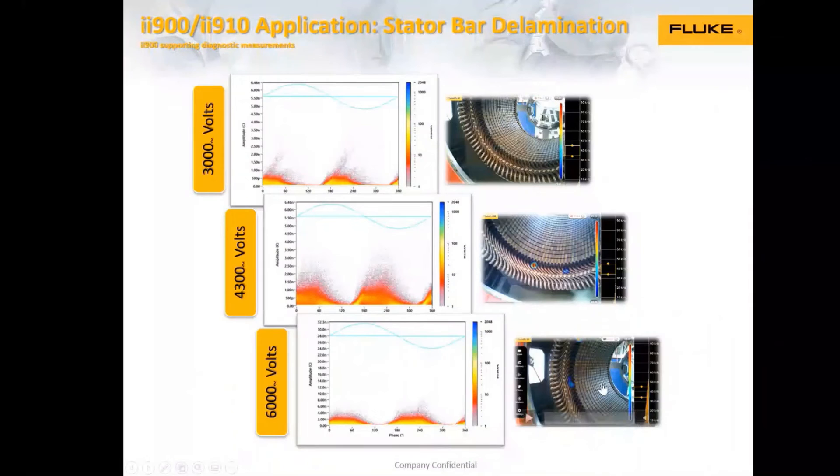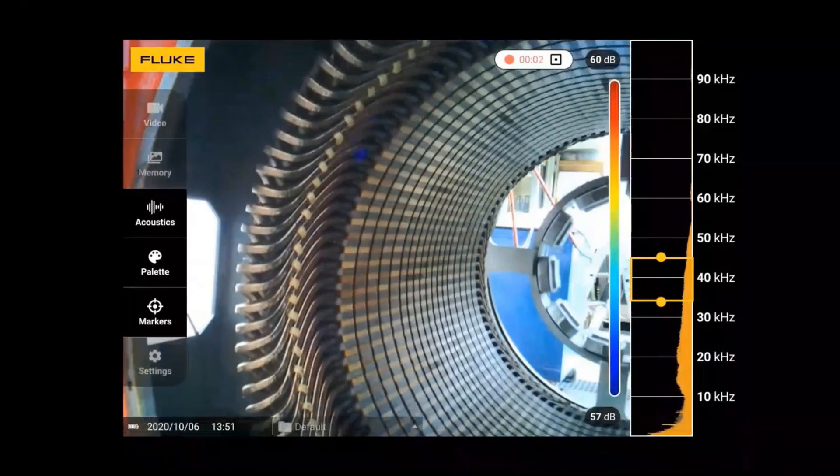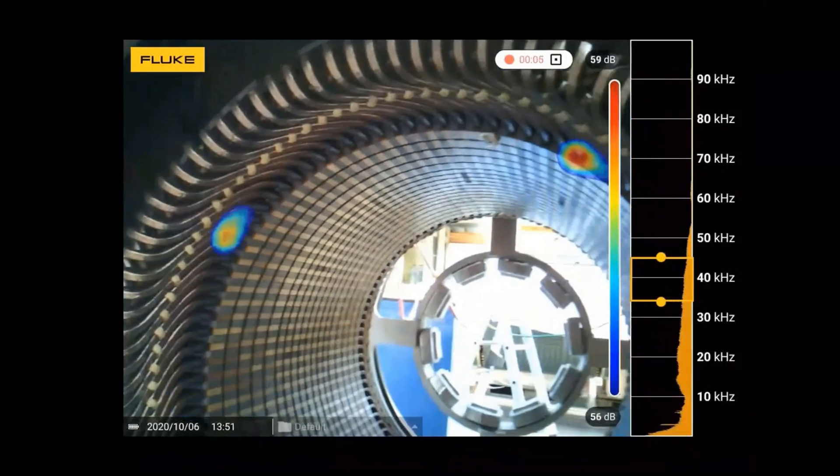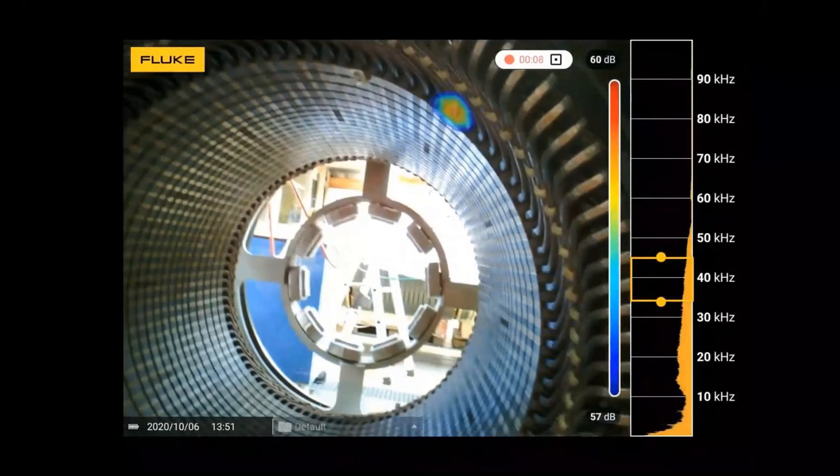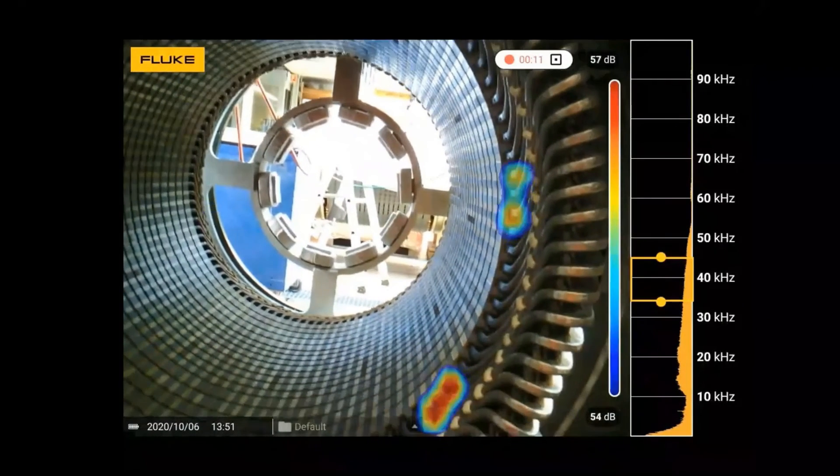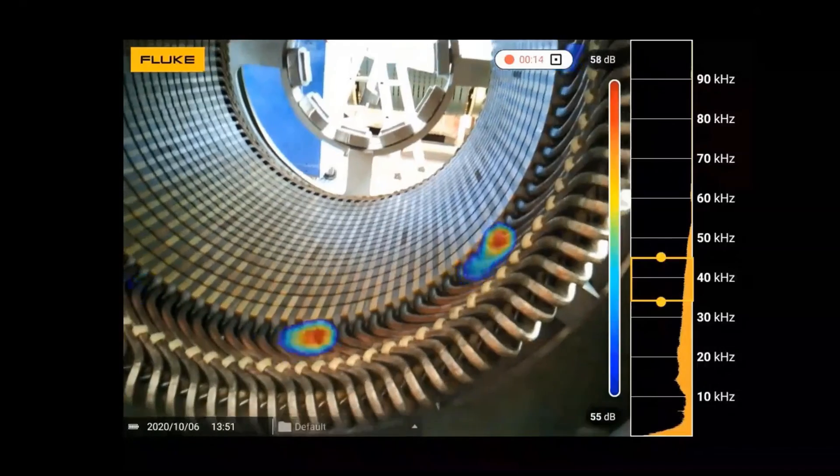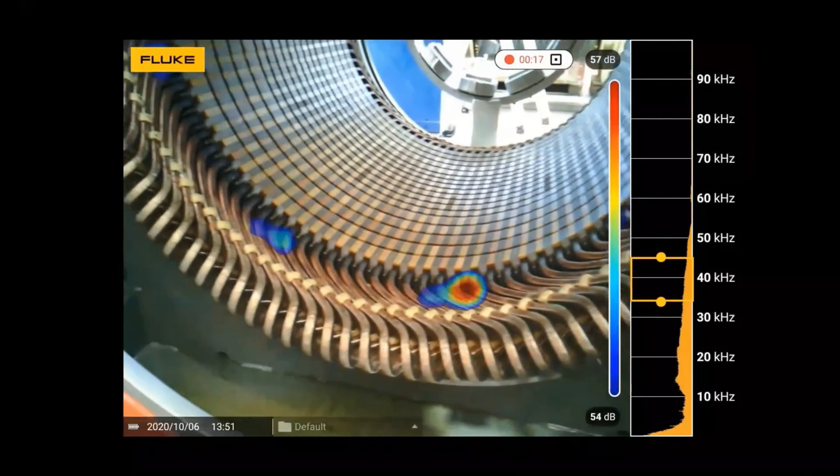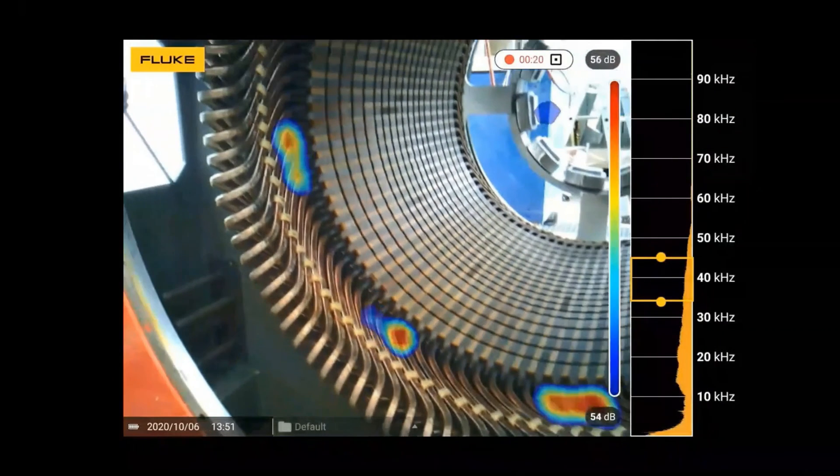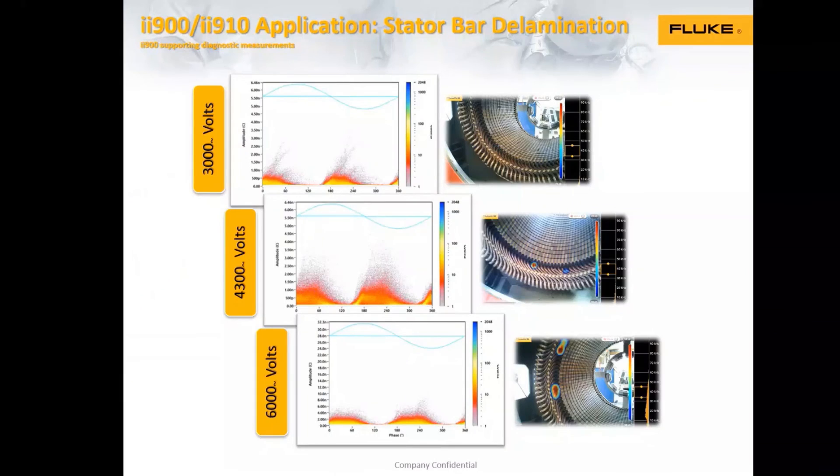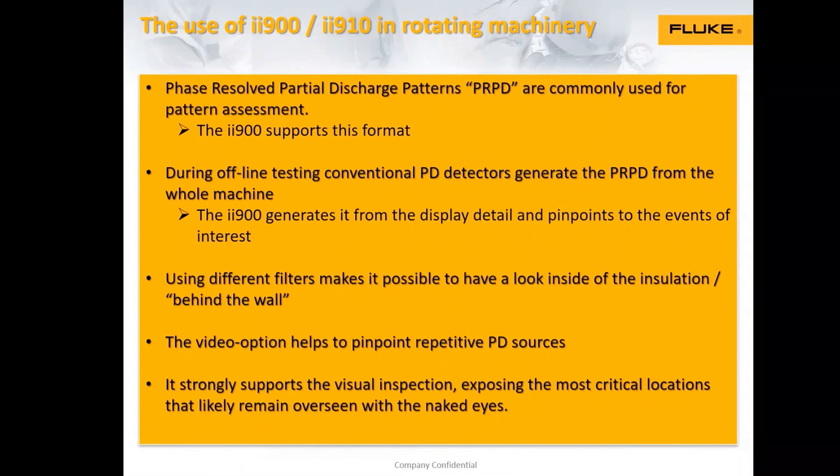And then the last one at highest voltage, now you see, because it's higher voltage, there's even more PD sources are triggered, and you see it's now generating PD all over. So again, if you have to make a repair and you have the chance to make a high voltage test, use the camera and you can see or identify the critical points that need the earliest repair or the most care. You can see with the camera relatively easy. So I come to a conclusion, phase resolved PD patterns are commonly used for pattern assessment and the camera is supporting this.